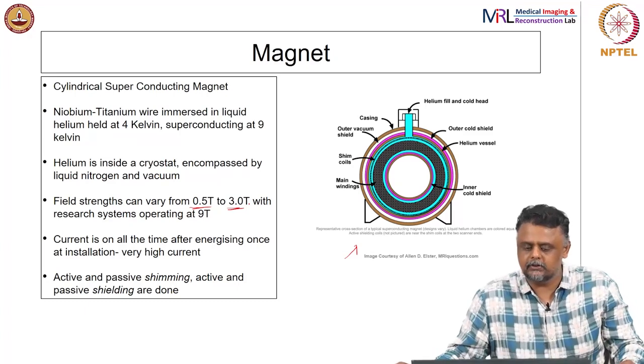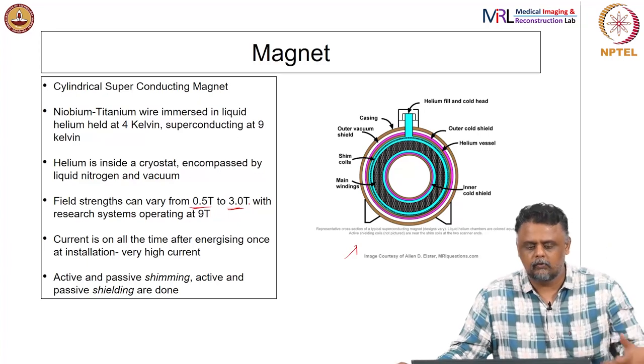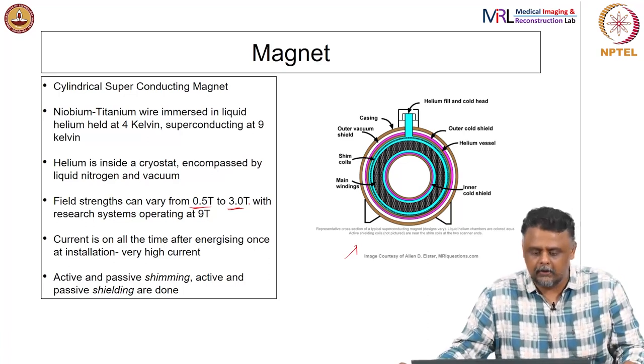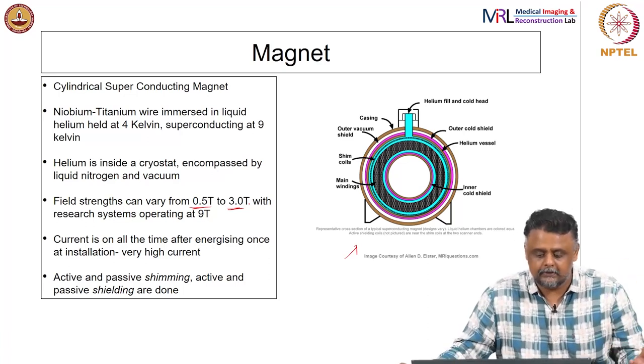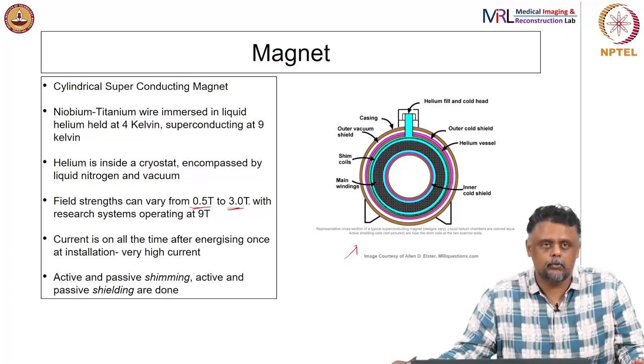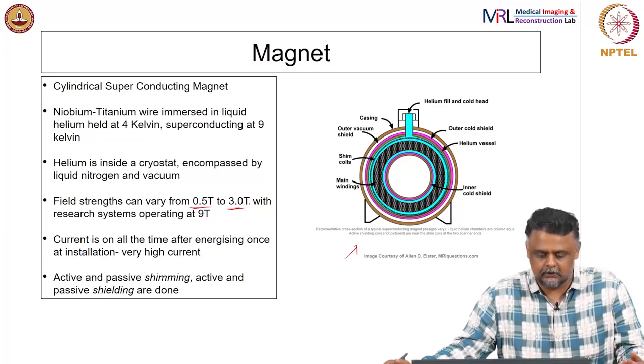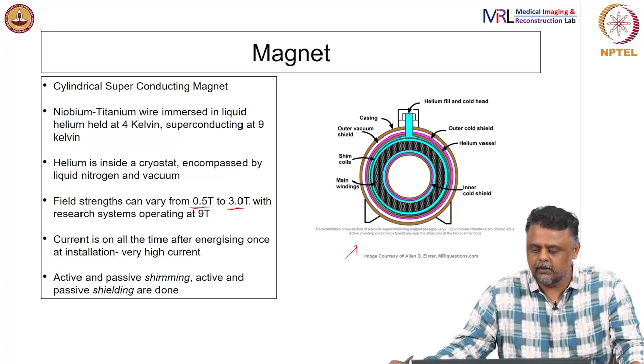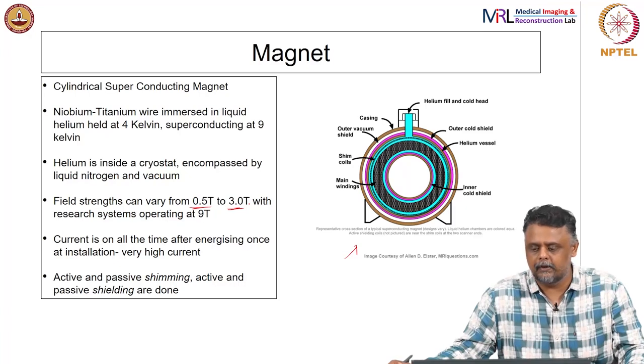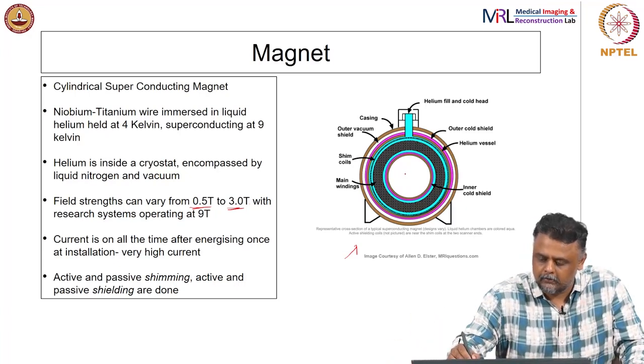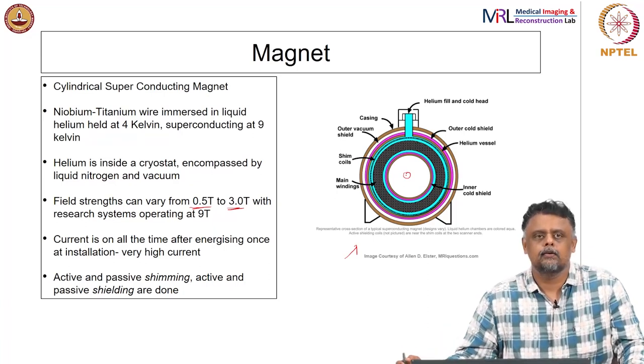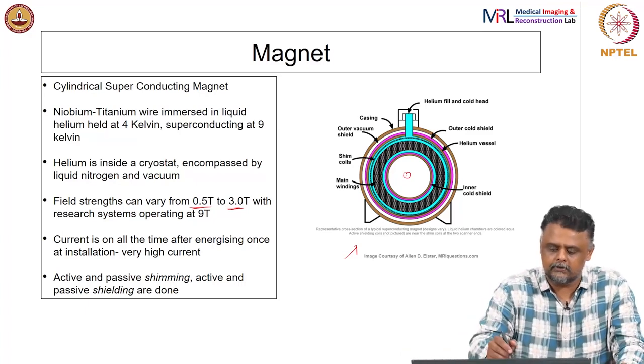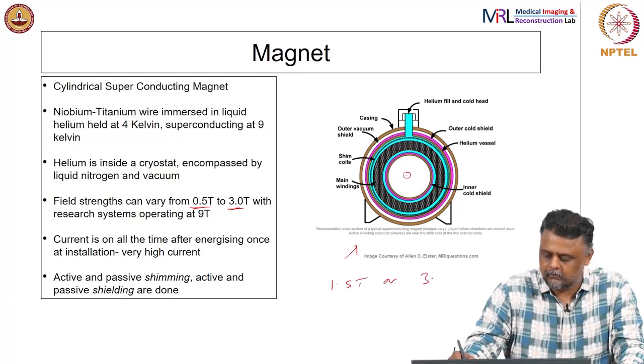The wire is wound around a cylindrical core and energized once. As soon as the critical temperature is reached, you inject current into it and the current keeps flowing because it is superconducting — there is not much loss due to resistance, though over time it will dissipate. This sets up a static magnetic field pointing along the axis of the core, typically 1.5 or 3 tesla for modern clinical magnets.